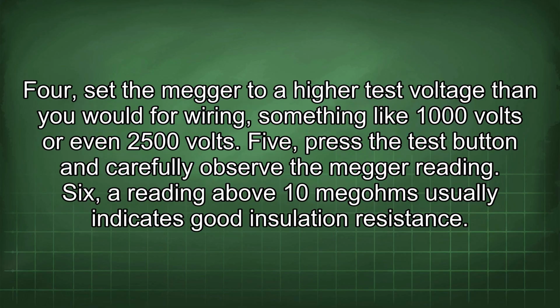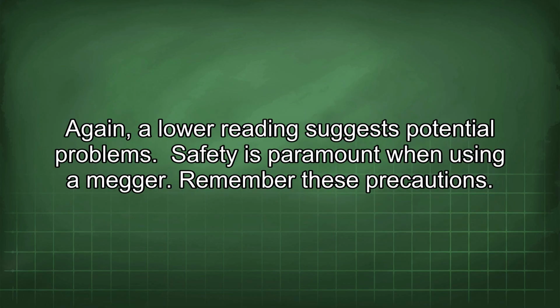4. Set the Megger to a higher test voltage than you would for wiring, something like 1000 volts or even 2500 volts. 5. Press the test button and carefully observe the Megger reading. 6. A reading above 10 megohms usually indicates good insulation resistance. Again, a lower reading suggests potential problems. Safety is paramount when using a Megger.